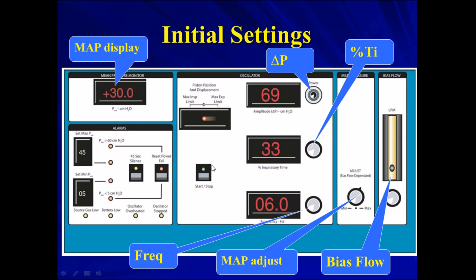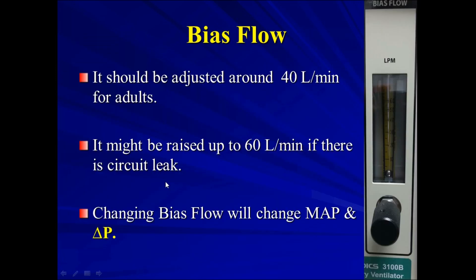Here we can start the machine and start the oscillation. For the bias flow, it should be adjusted around 40 liters per minute for adults, and for pediatric it's around 20 liters per minute.